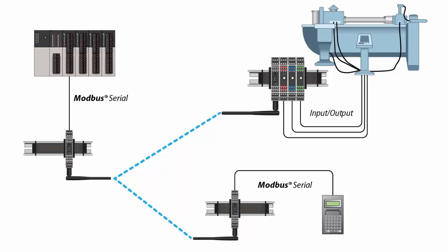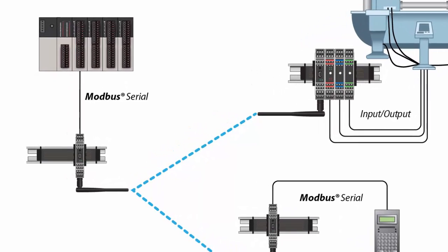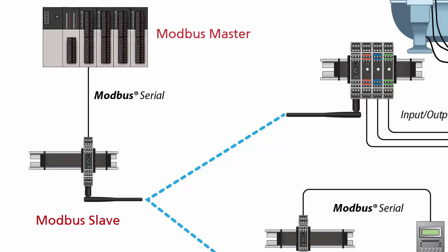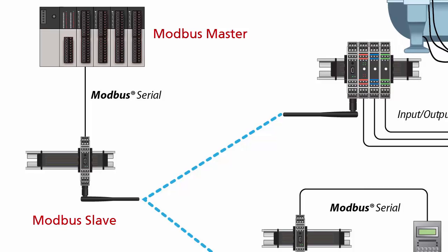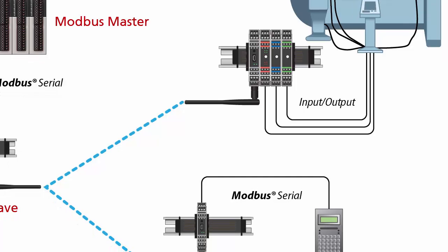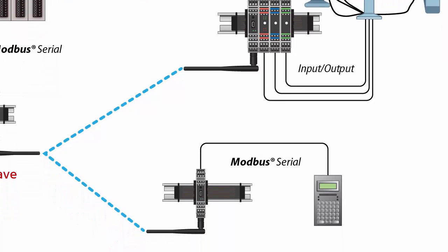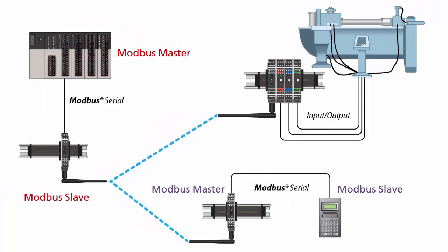A standalone multi-point wireless I.O. gateway acting as a Modbus slave with a PLC acting as a master will drive outputs on a gateway with remote I.O. and will read and write data to another gateway acting as a Modbus master connected to a Modbus slave device. Since the primary gateway does not have any I.O. expansion modules, input and output data will be in the form of registers controlled by our Modbus master, in this case a PLC, in our control center.